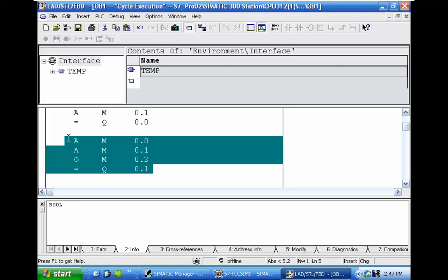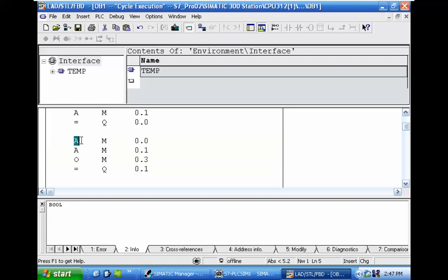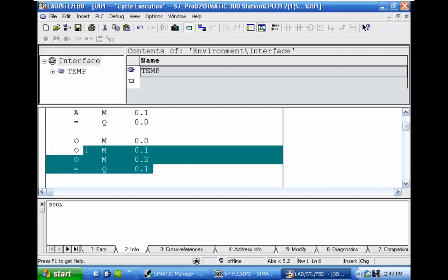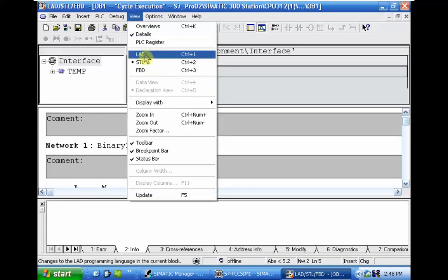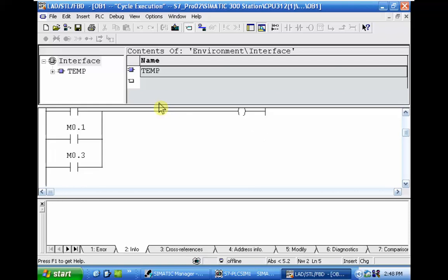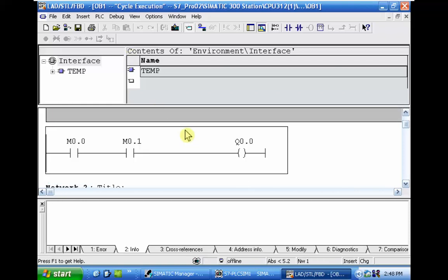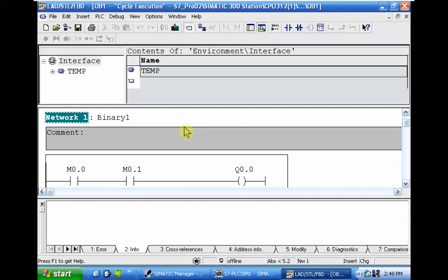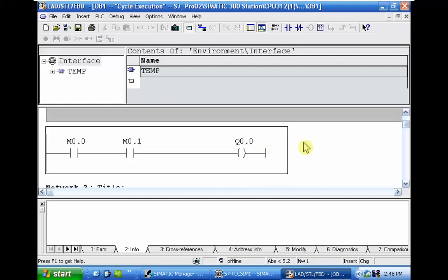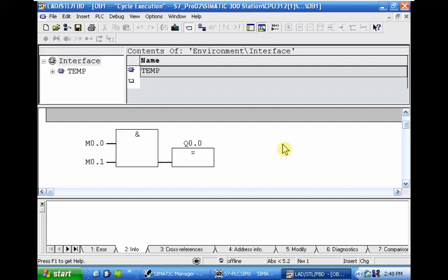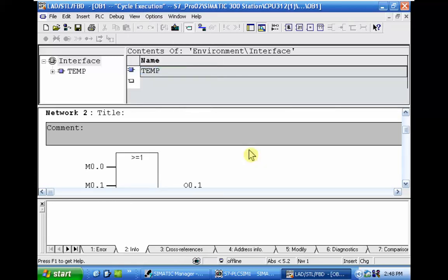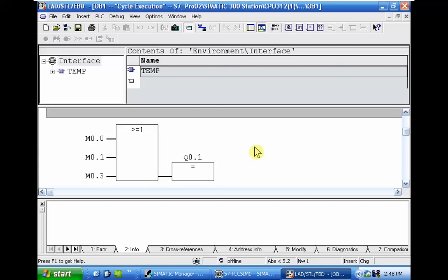To convert, we need to perform the separation of logic steps. I'll change all of them and copy the second logical step and insert it here. If you are familiar with the concept of logical steps in STL, you can perform separation of logical steps in your program, and the program will then be available in ladder, STL, and FBD. You can switch the programming languages from here.